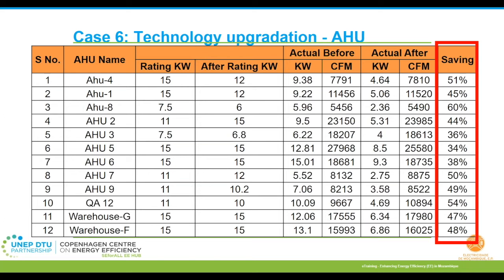the deliverables are not compromised, and rather you have this improved, and the power consumption to deliver the same flow is reduced, almost like from 36% to 60% in certain cases. So this is something you may also look into for the ventilation systems. The only thing you need to consider here is the availability of this technology for a wider range of static pressure requirements.